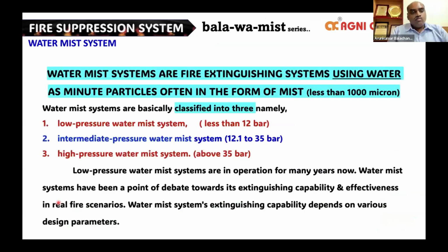We will now move to the water mist technology. As the name suggests, water mists are using water as an extinguishing agent in the form of mist. So what the standard says is any water droplet that is less than 1000 micron is classified as mist. This is as per all global standards.